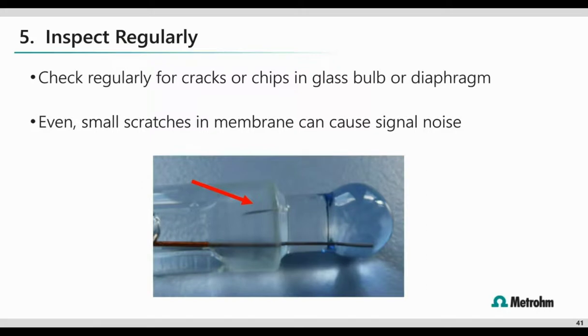Number 5, inspect regularly. We heard earlier how important the membrane and diaphragm are in making accurate measurements. I would encourage you to get familiar with these key parts of your electrode. Pull them out and inspect them. Ensure there aren't any cracks. It's good practice to inspect them before every time you use them.